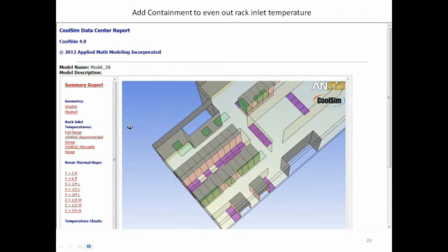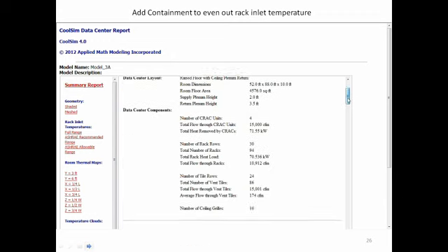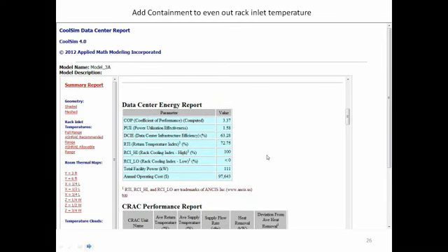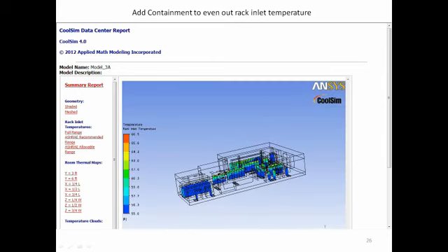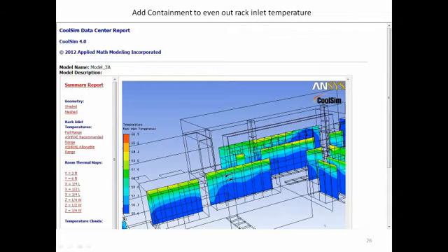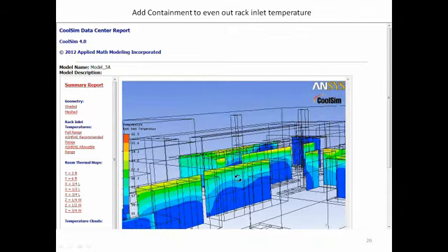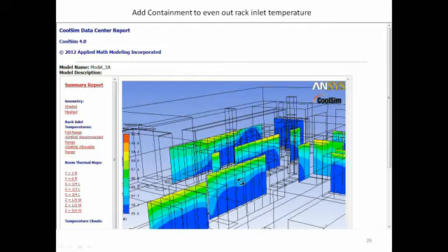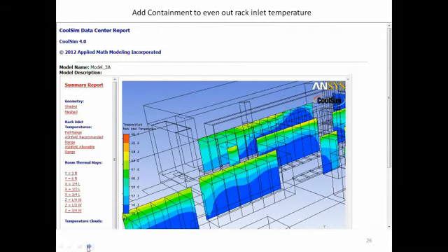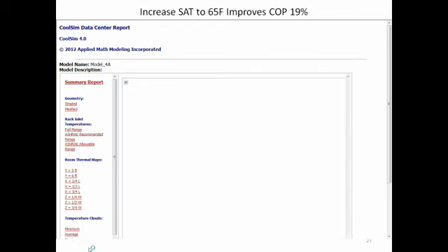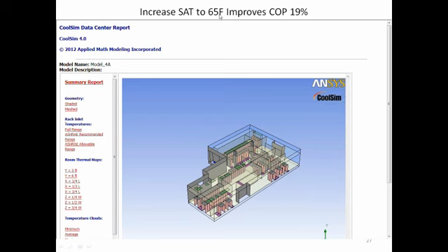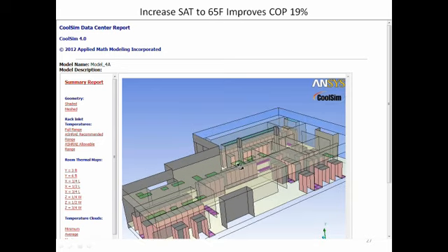You'll see that from an energy point of view, nothing changed, because we didn't change anything with respect to this area right here. The curtains don't do anything in this region. But with respect to temperature, things are a little more uniform now. You see how the racks are a little more uniform than they were. So we're doing a better job managing air than we were earlier, and that helps as we begin to raise temperature. Once we've got the curtains in place and done a little management, we can begin to drive up supply temp. Here we're driving supply temp up to 65 degrees. Let's see how we do with respect to conformance.